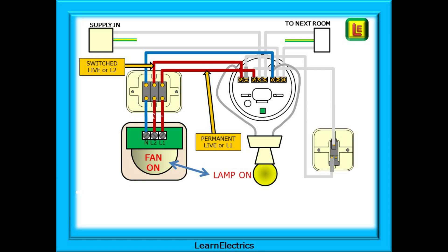There are two lives or phases to connect. The permanent live is taken from the live loop in the ceiling rose, through the switch, and into the first of the live terminals on the fan, marked here as L1. The switch live comes from the ceiling rose, through the switch, and into the second live terminal on the fan, marked L2. Then the neutral from the ceiling rose, through the switch, and into the N on the fan. Finally, make the necessary CPC or earth terminations.